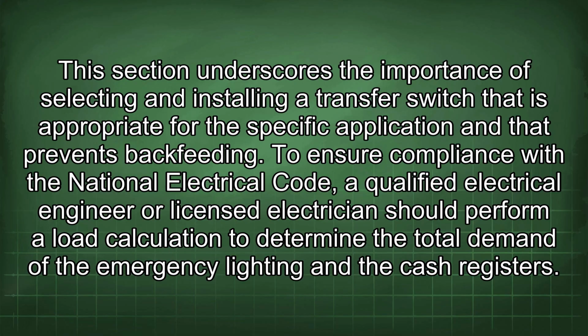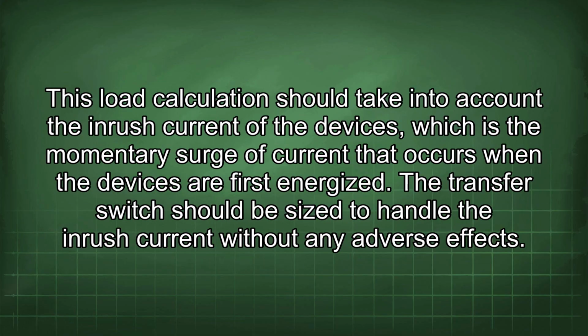To ensure compliance with the National Electrical Code, a qualified electrical engineer or licensed electrician should perform a load calculation to determine the total demand of the emergency lighting and the cash registers. This load calculation should take into account the inrush current of the devices, which is the momentary surge of current that occurs when the devices are first energized. The transfer switch should be sized to handle the inrush current without any adverse effects.